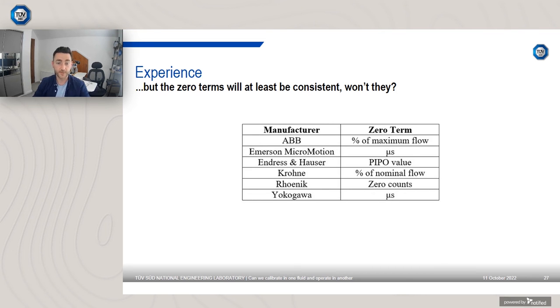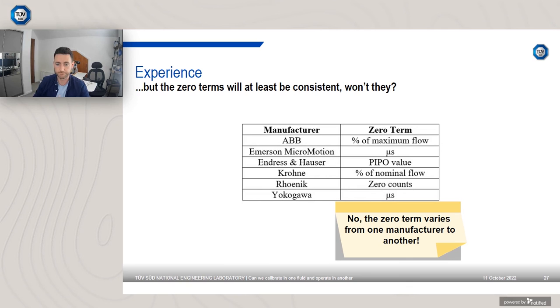So straight away you can see that terms are not consistent, and that is quite challenging as well, because if you're used to using one and then you have a completely different model or manufacturer and it has a different zero term, it can be slightly confusing. You have to refer back to the manufacturer's guidelines for further information. So no, the zero term varies from one manufacturer to another, which is a bit of an annoyance.